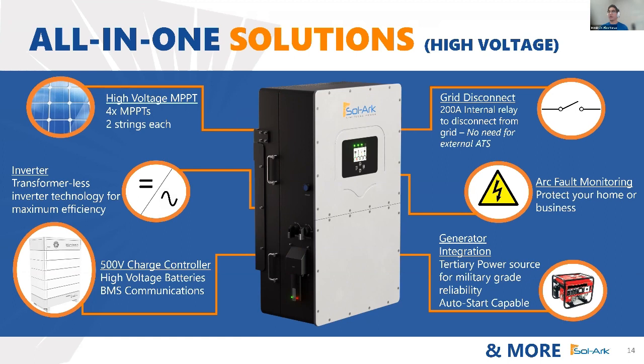We do also have a grid disconnect. So 200 amp internal relay, it is integrated in the unit in the lower right here. And so again, you don't need an external ATS. However, you can use one if you need it to connect to a generator to the grid, or depending on the case use that you have. If you have any questions on these case studies, you can always reach out to us and we'll be happy to discuss.